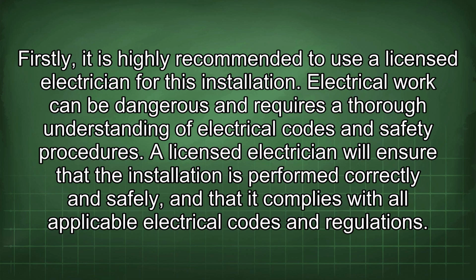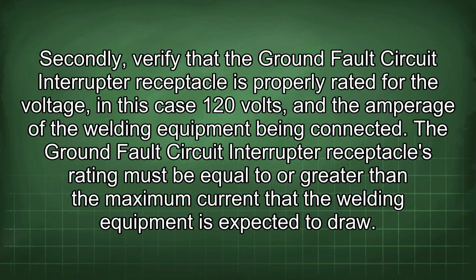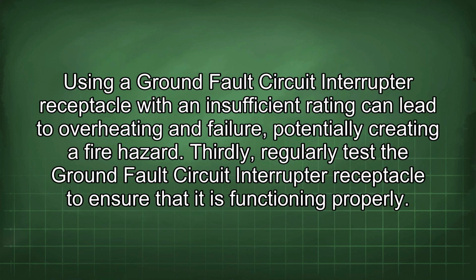Secondly, verify that the ground fault circuit interrupter receptacle is properly rated for the voltage, in this case 120 volts, and the amperage of the welding equipment being connected. The ground fault circuit interrupter receptacle's rating must be equal to or greater than the maximum current that the welding equipment is expected to draw. Using a ground fault circuit interrupter receptacle with an insufficient rating can lead to overheating and failure, potentially creating a fire hazard.